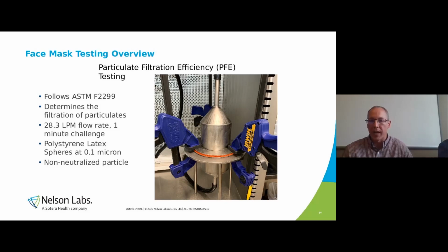These particles are not neutralized. They carry a charge as opposed to the 0.3 micron particles we use in the respirator testing. So these particles are easily filtered out of the air because of the charge of the face mask material. It will attract the particles based on that charge and filter them out a little bit easier. And we are also only pulling a 28.3 liter per minute flow as opposed to the 85 liter per minute flow of the respirator. So you might think that this test is more stringent than the respirator test because of the small particle size, but it actually isn't due to the flow rate and also the charge of the particles, which helps in filtering it out. As you can see, we are testing a flat sheet as well. We will not test the full respirator, so we do require a flat sheet material when it comes to this test.